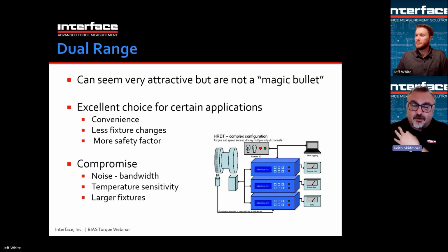They are compromised though. It can be noisier. The low range does have more gain on the signal, so any noise in the system does get amplified. Typically, you want to run heavier filtering. That may not be desirable depending if you're trying to measure something with high bandwidth. Temperature sensitivity, the lower range is more sensitive to temperature. And then again, you have large fixtures.